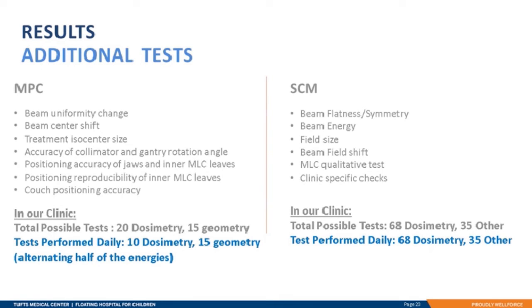Machine Performance Check, on the other hand, assesses the accuracy and the reproducibility of just the inner MLC leaves. As we've previously discussed, SunCHECK Machine also allows for a lot of customization to add any clinic-specific checks. So for our clinic, we've added certain checks for machine parameters like gas pressure and water level, as well as our daily QA for our surface guidance system.